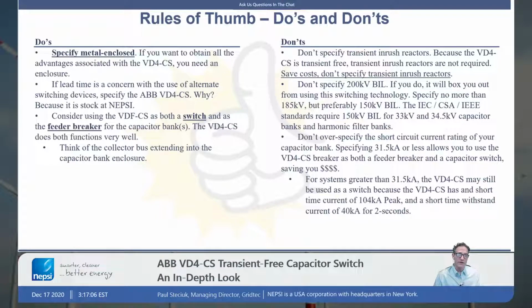Don't over-specify the short circuit current rating. We oftentimes get specifications and they automatically go to 40 kA. We go back to the customer and say, can you confirm 40 kA?